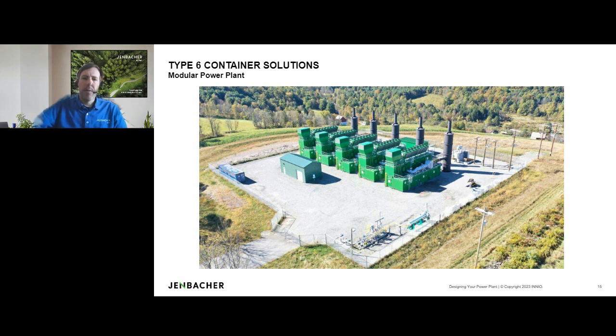We provide the containerized system, which includes the SCR, that's the little gray box there. Then really all that's needed at site is a silencer. Depending on the configuration, the silencer can be either located on the unit or next to it, behind it, with the stack there. And then you would have a centralized fluid storage system here, which would be for your urea and lube oil for the engines. In the background would be your 13.8 medium voltage power distribution center, as well as the auxiliary low voltage distribution, gas supply down here, and your step-up transformer up there.